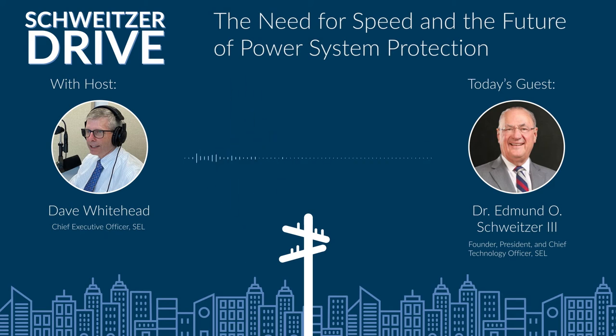So there's certainly a lot of benefits for phasor-based protection. You were able to essentially calculate phasors to do the calculations for if there's a fault on the power system. Are there some limitations though to phasor-based protection, or should we just continue to use phasor-based protection from here until the sun goes dark?